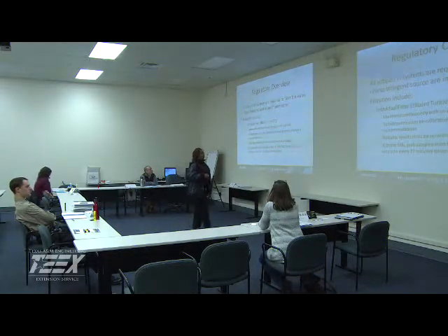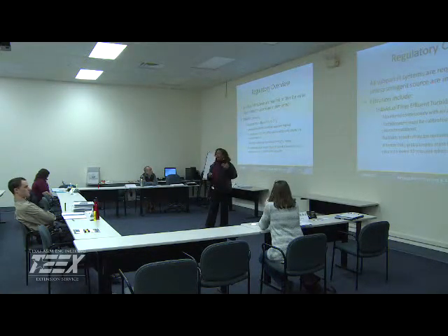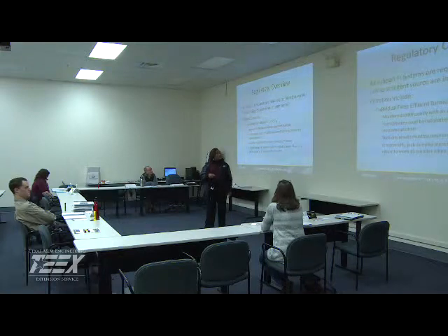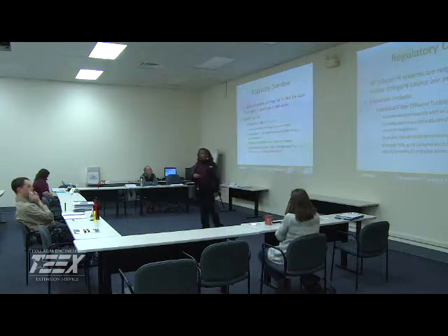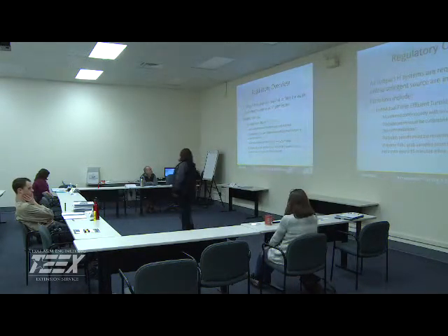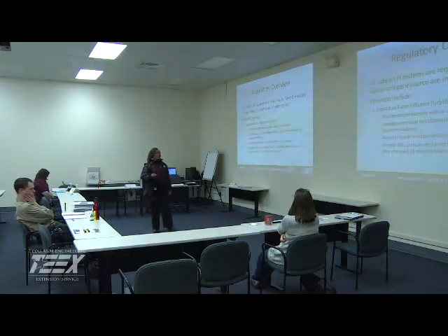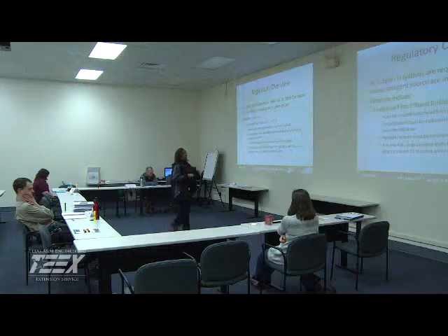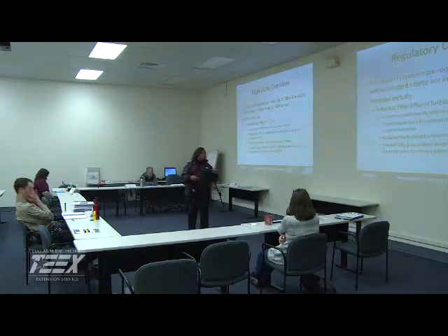For individual filter effluent turbidity, these are monitored with a continuous approved method, and your turbidity meters must be calibrated according to the manufacturer's recommendation. Here, we're looking at turbidity readings every 15 minutes, not the 4 hours, but every 15 minutes for your individual filters. Now, if your meter failed, they will allow you to go to every 4 hours. However, you have 5 days to get that meter back online.